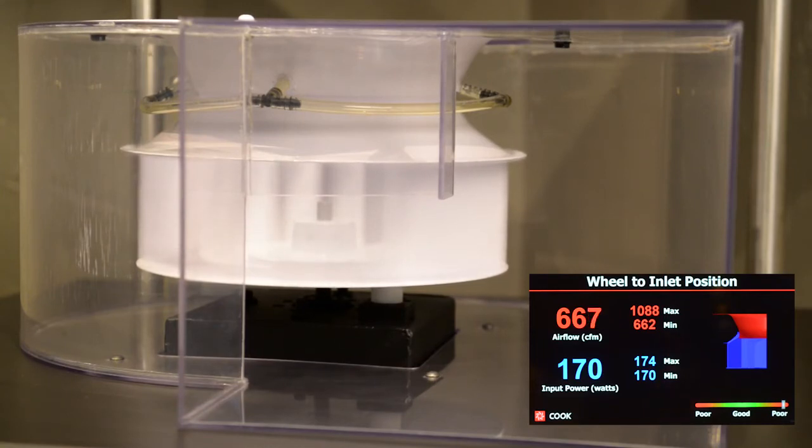This is because the wheel is doing the same amount of work, but some of the air is leaking back into the inlet of the wheel, a low pressure area, from the discharge, a high pressure area.